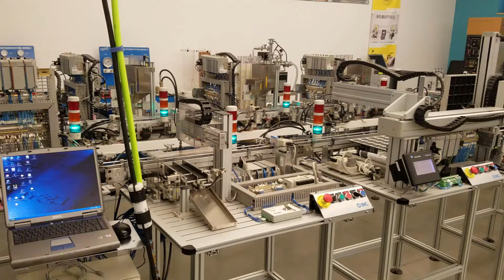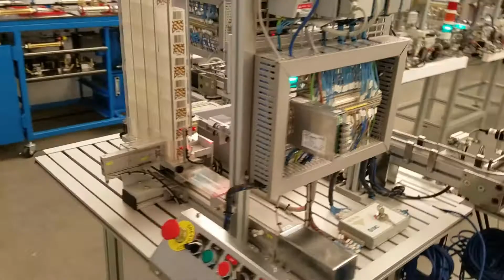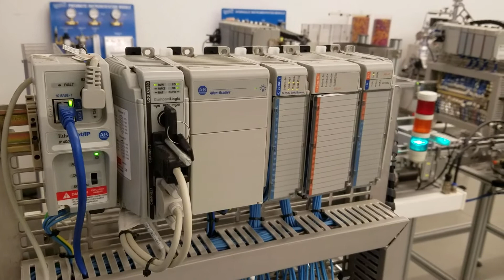Okay, I'm going to give you a brief tour of the SCADA hardware on the HAS 200. So, to have a SCADA system, SCADA meaning supervision, control, and data acquisition, you need to have sensors on the system that are delivering some kind of information back to either a controller, a PLC, or another type of unit called a remote telemetry unit, RTU.